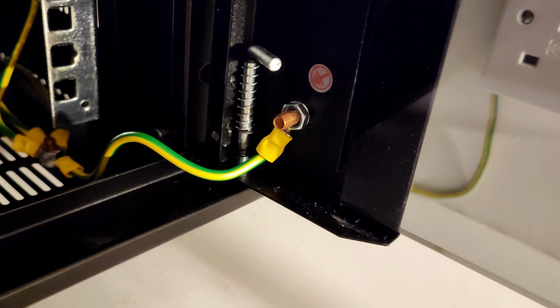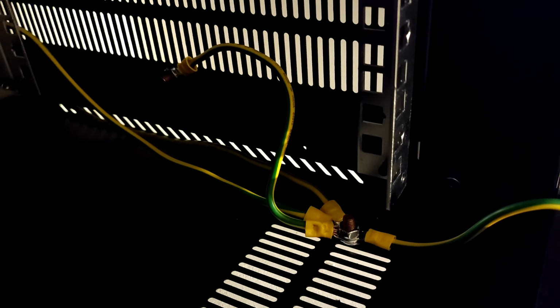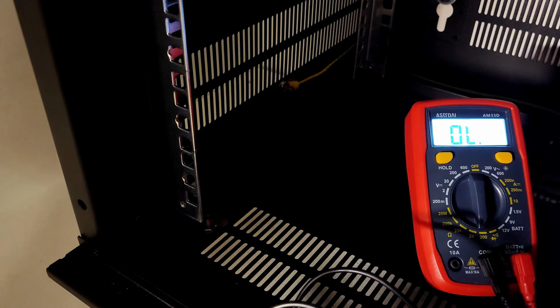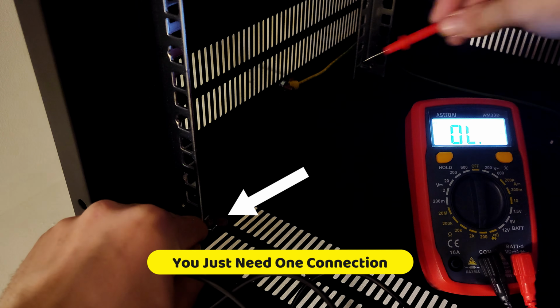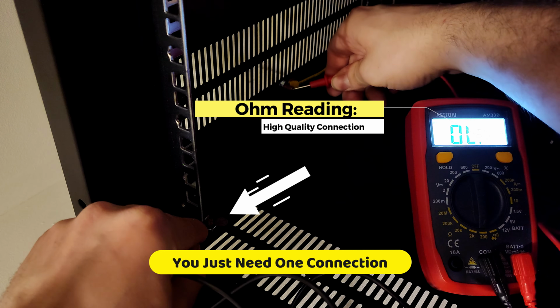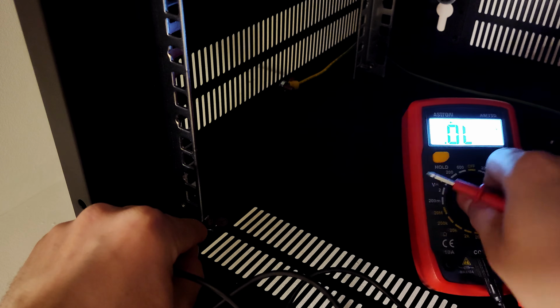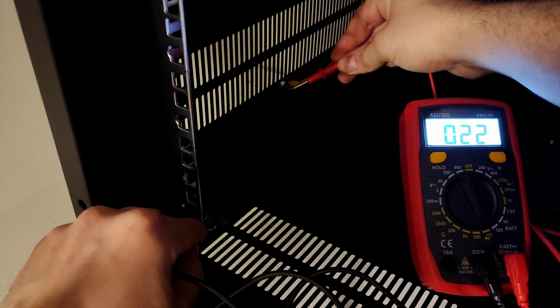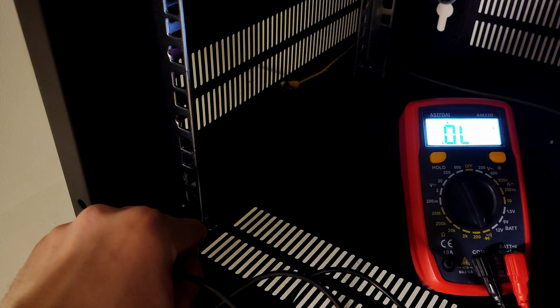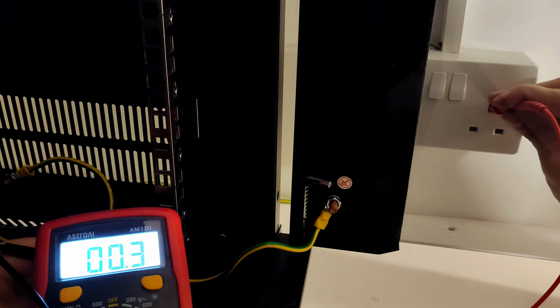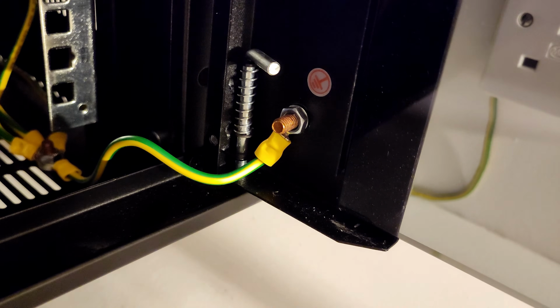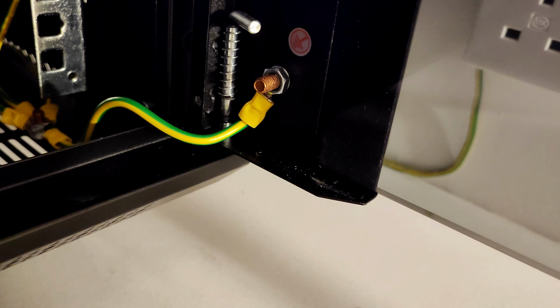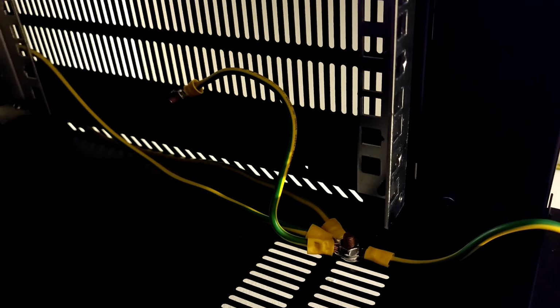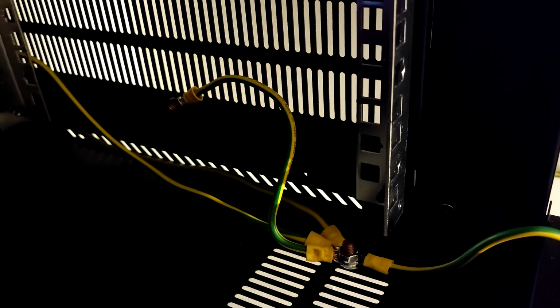Bonding all panels together ensures that every part of the rack is at the same electrical potential. This minimizes the chance that a fault or a stray voltage will create a dangerous voltage difference between parts of the rack. A well-bonded chassis helps to reduce electromagnetic interference and the formation of grounding loops. Even though your equipment is already grounded, bonding all panels of your server rack creates a robust and uniform grounding system. I attach this cable from each panel to the main board, which is directly connected to the grounding from the socket. This method creates a star grounding configuration where every grounding path converges to a single center point.